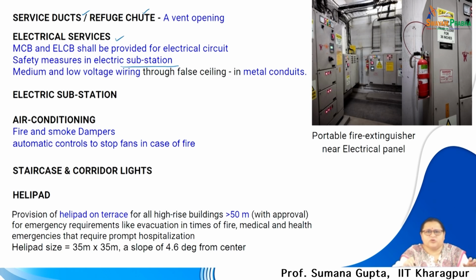Any medium and low voltage wiring should not be neglected; wiring that passes through false ceilings should be in metal conduits, and no wooden items should be used in the entire system. We have already discussed the air conditioning system in the previous module, including the actuators and sensors which initiate the smoke damper or fire damper, which should be automatic in nature and should stop the fan in case of fire and stop the smoke movement by closing the louvers kept between compartments.